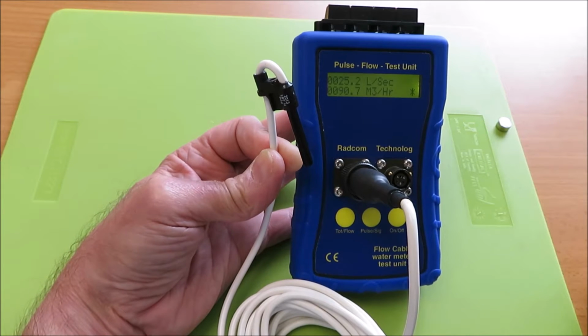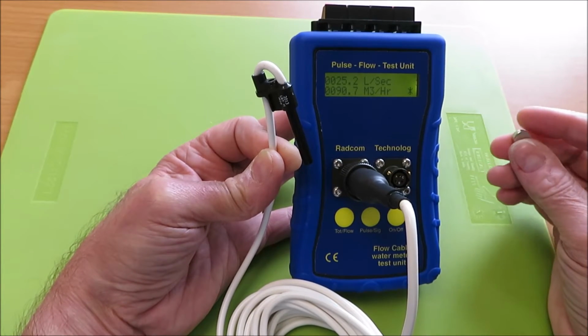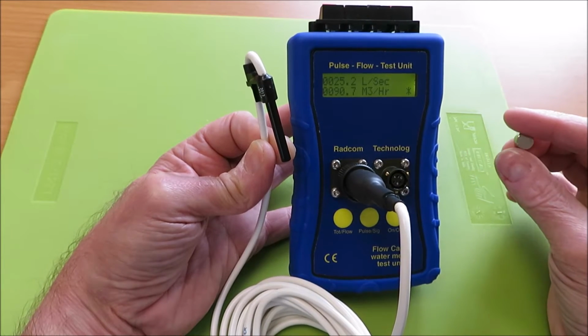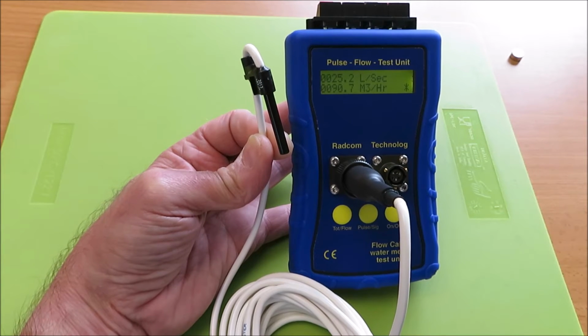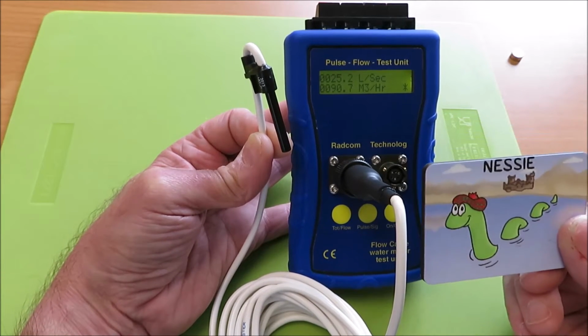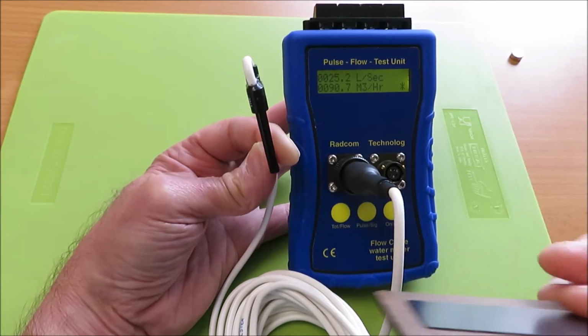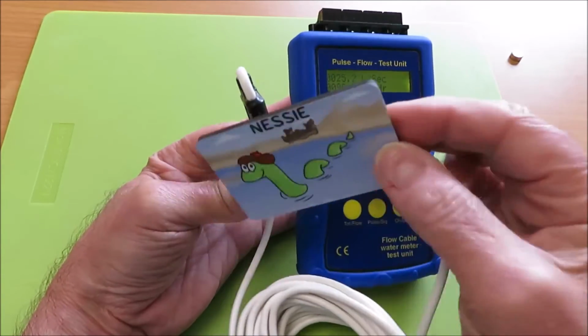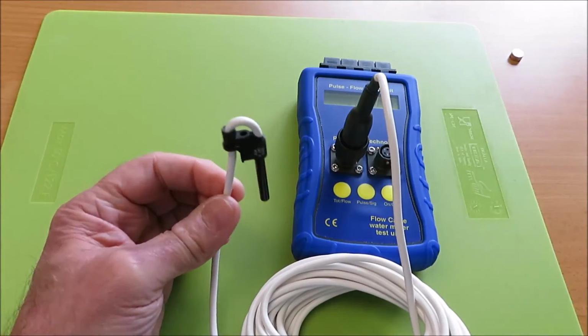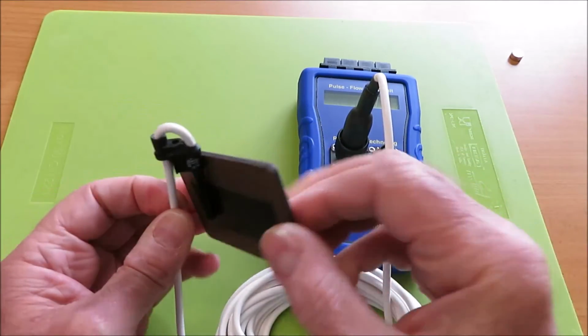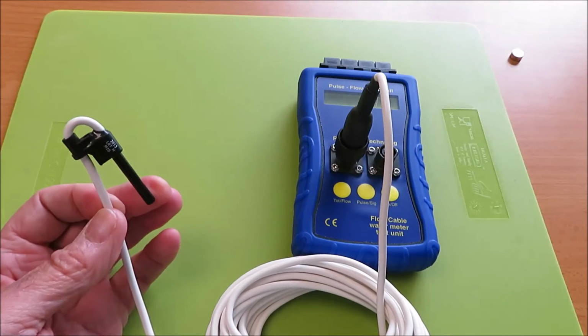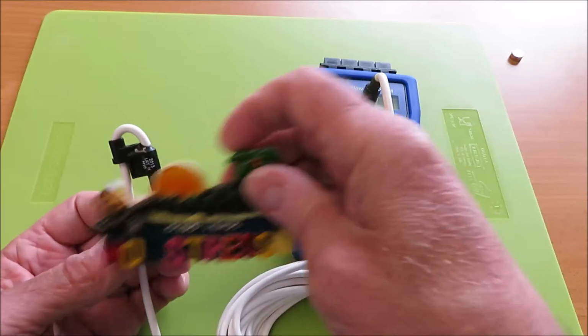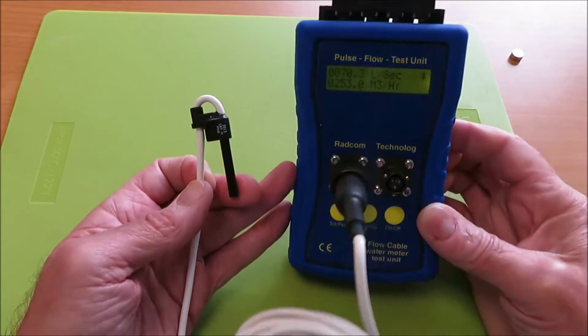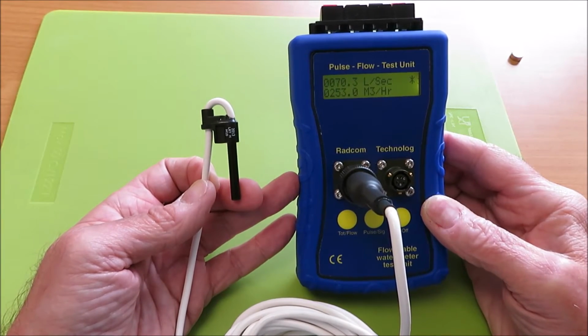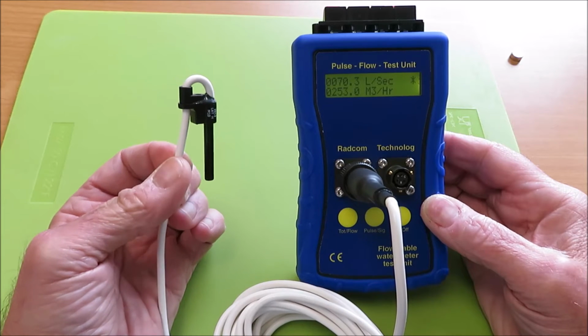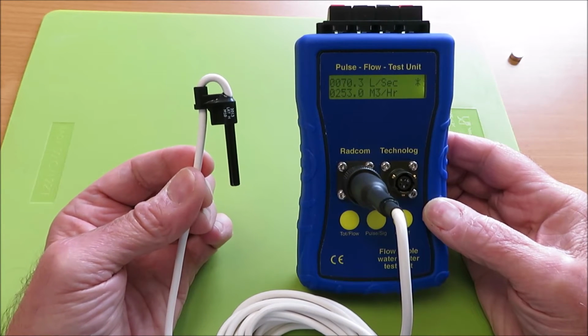Now, depending on where you are in the country, obviously you need specialised equipment to test the reed switch type flow test units, and if you're in Scotland you would need this, or is it just a magnet? And again, just by passing the magnet in front of the unit, it is possible. So no real specialised equipment is required to get a pulse. Any basic magnet will operate and give you a flow rate, and that's the basic reed switch type flow sensors. They would all operate in that manner, that you would need a magnet.